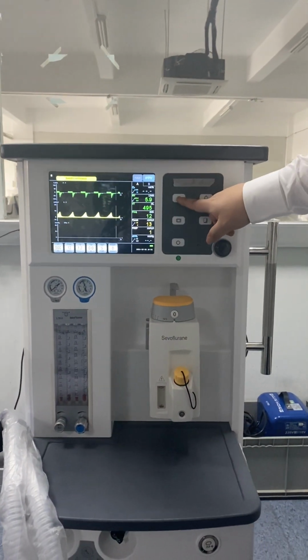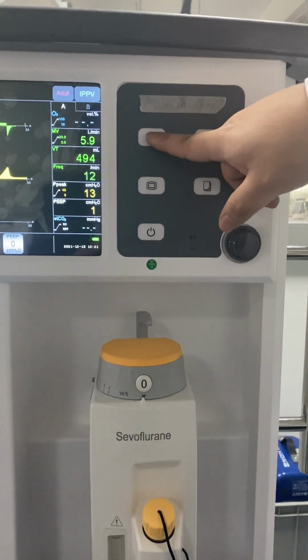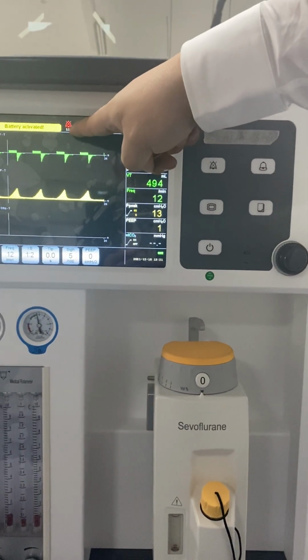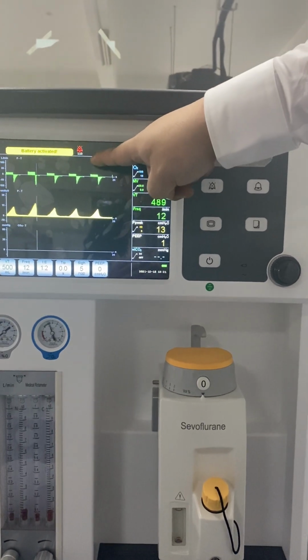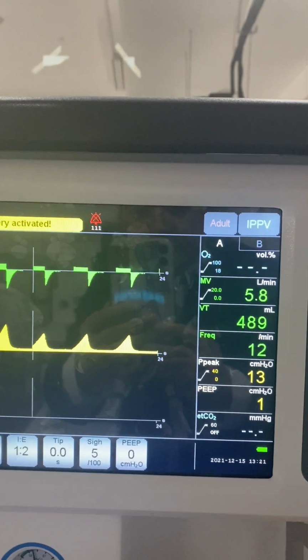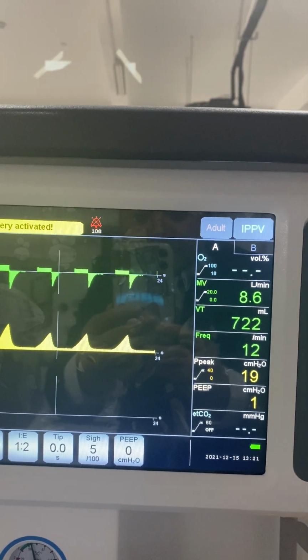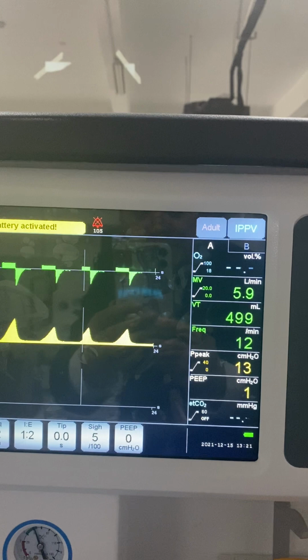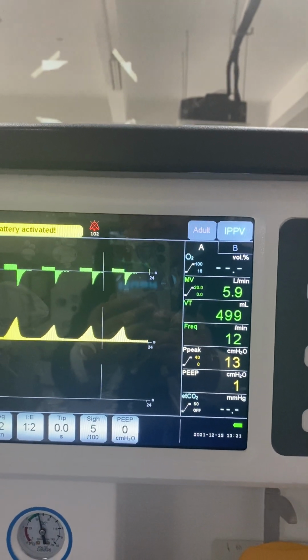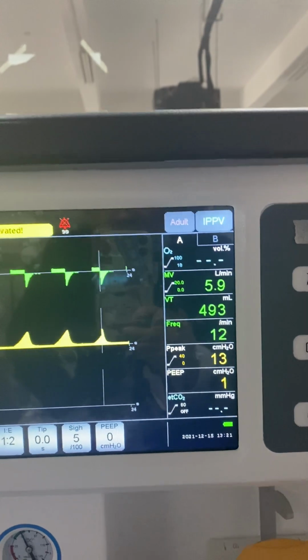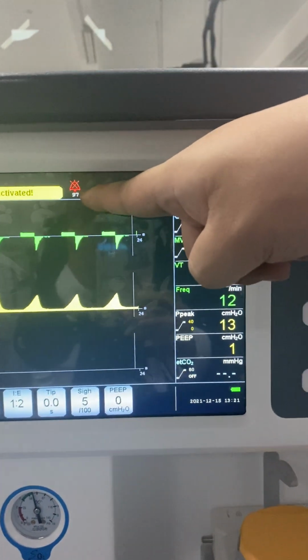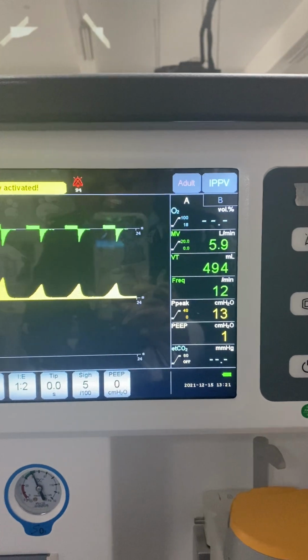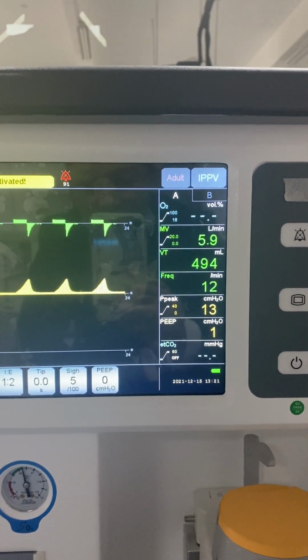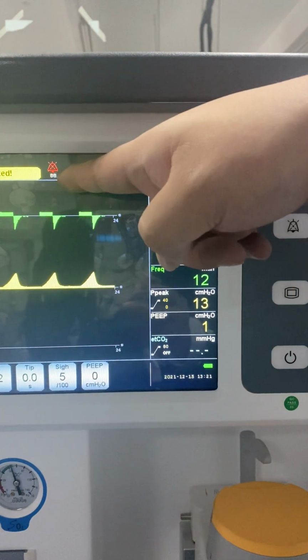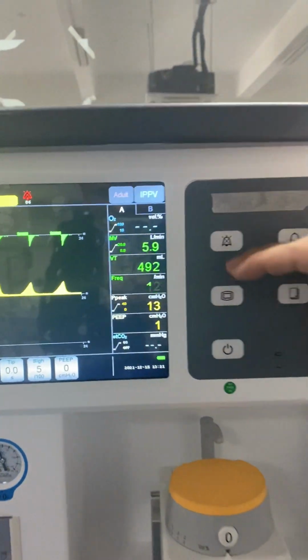For the buttons here, you can see the first button is for mute. Once we press it, you can see on the screen at the top side there is a 2 minute time count. That means for the next 2 minutes there will be no noise or alarm from the anesthesia machine. So the doctors can do the operation in a very silent condition, and the patient will not be disturbed. But after 2 minutes, the alarms will come again, because we must ensure that if the doctors forget to turn it on, the patient will not be in a dangerous condition. If you want to stop the mute, you can just press this again. Then it will give the alarm again.